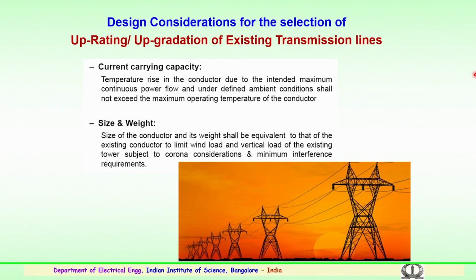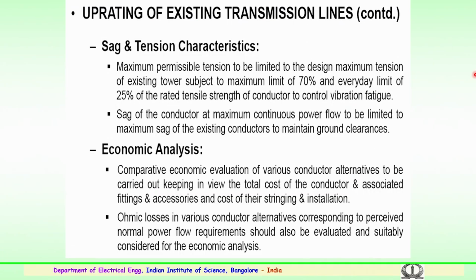So, in the case of uprating of the conductor, the mechanical strength and weight of the conductor should be similar to the previous conductor which is being replaced, and it should also be able to limit the wind load and vertical load on the existing tower. It must also meet corona considerations and minimum interference requirements like RIV, or the corona inception or extinction voltage levels at that operating voltage, as were required earlier for the ACSR type conductors. So, the uprating or upgradation of the existing transmission lines is very important.